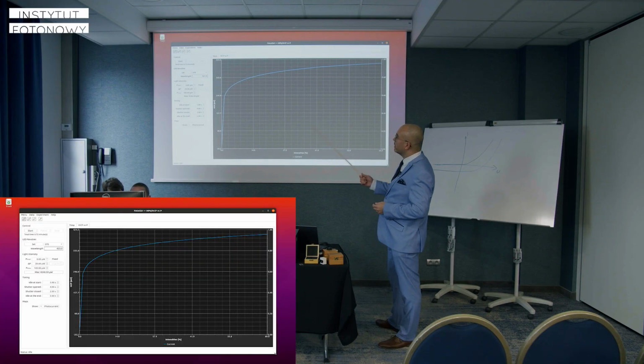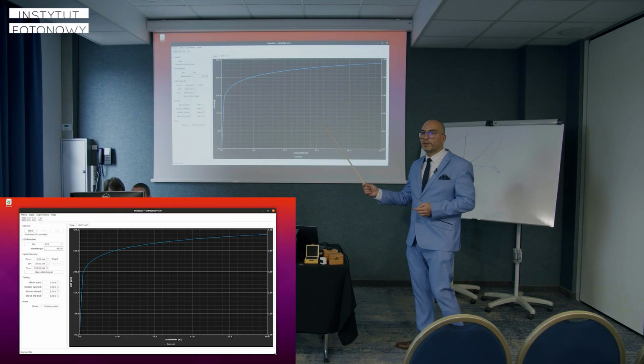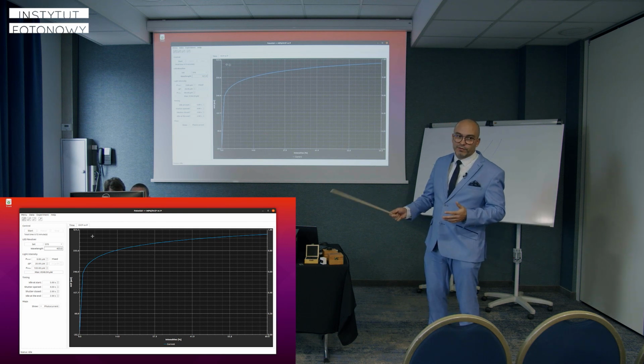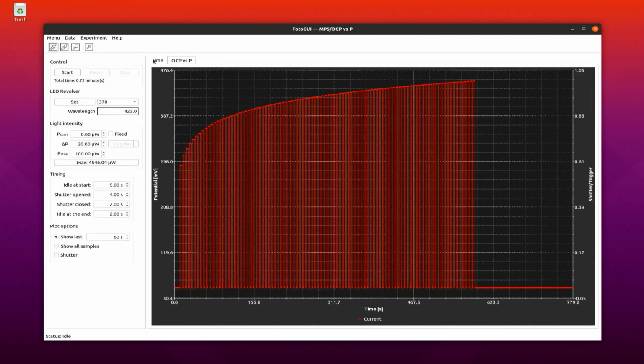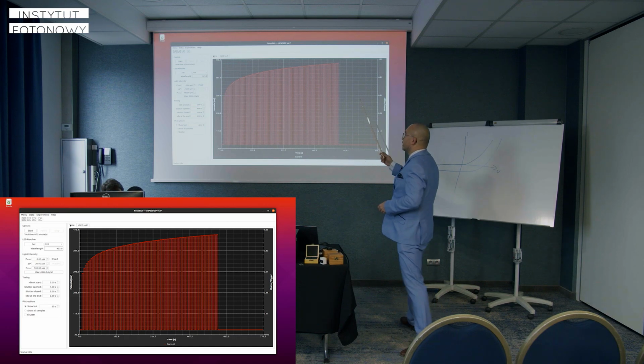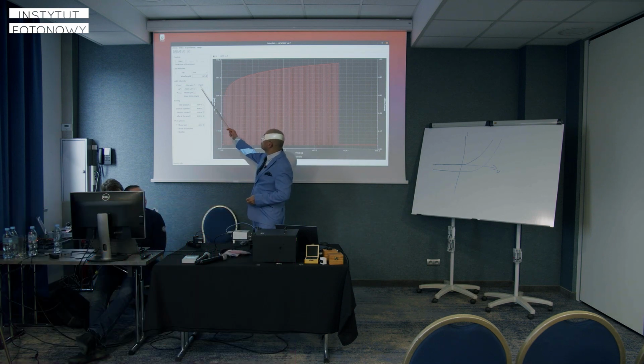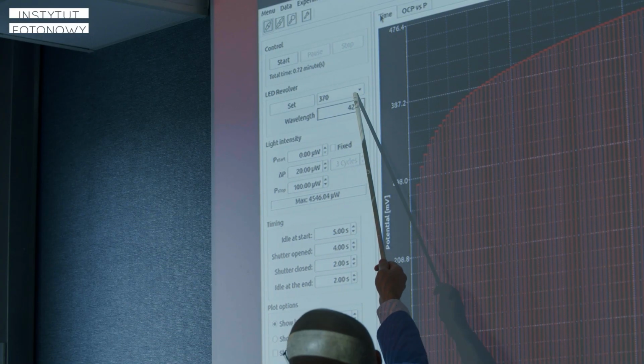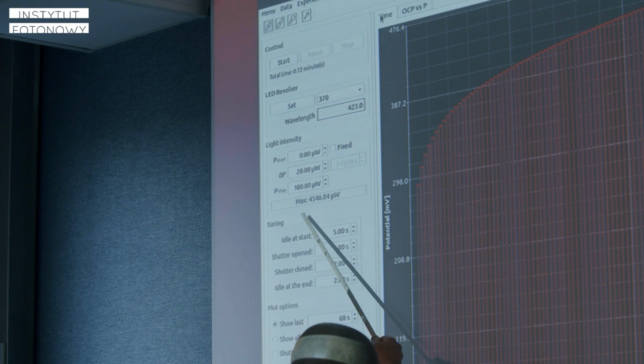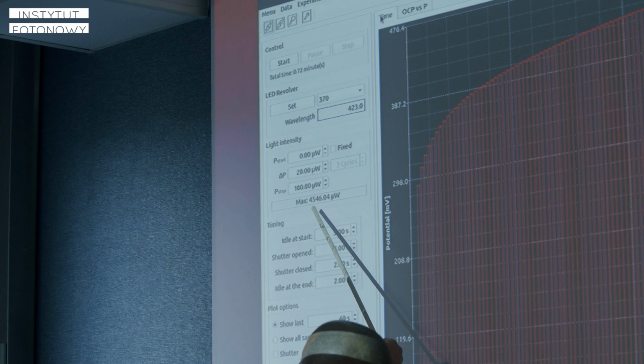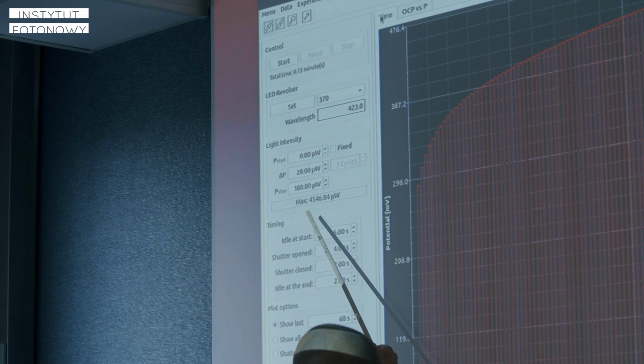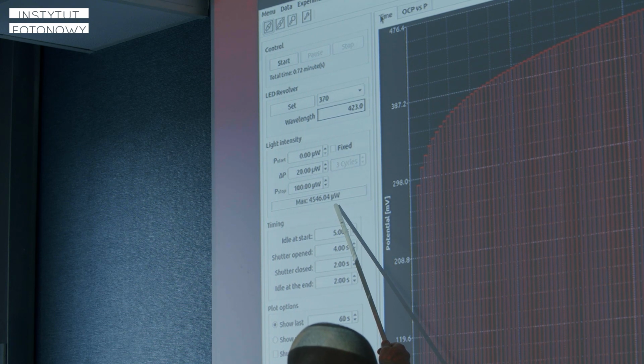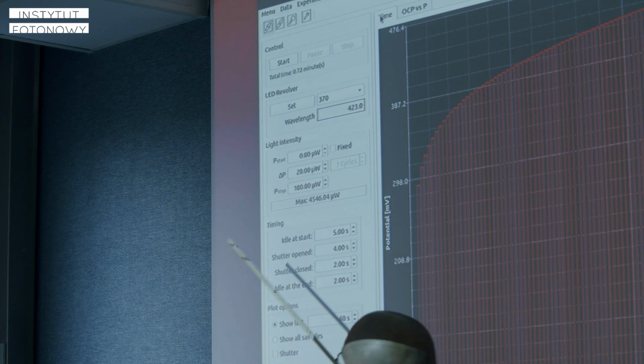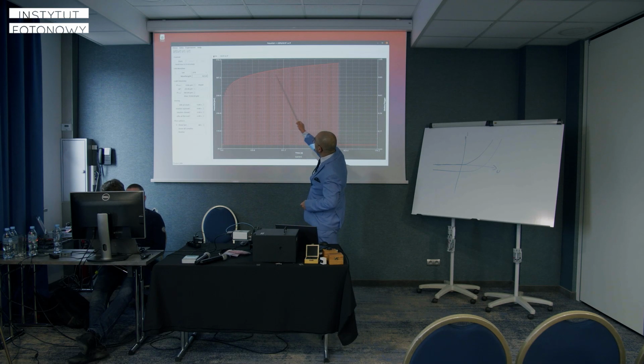So again, we can select for which wavelength we perform this experiment, because for different wavelengths the OCP, the sensitivity of our sample may be different. We define the range of initial light power from, say, 0 microwatts up to, for this LED, for this wavelength, the maximum available power, 4,500, so 4.5 milliwatts, with the step. The denser the step, the better, the more fluent this profile is.